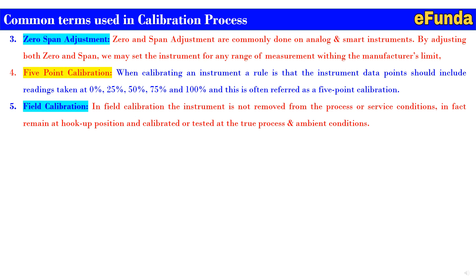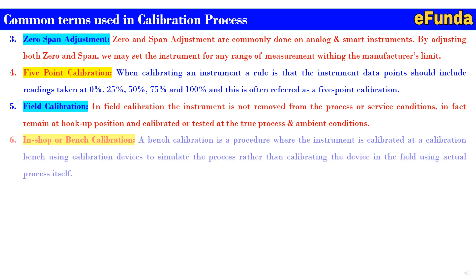Fifth is field calibration: the instrument is not removed from the process or service condition. It remains at the hookup position and is calibrated or tested at true process and ambient conditions. Sixth is in-shop or bench calibration: this is a procedure where the instrument is calibrated at a calibration bench using calibration devices to simulate the process, rather than calibrating in the field using the actual process itself.